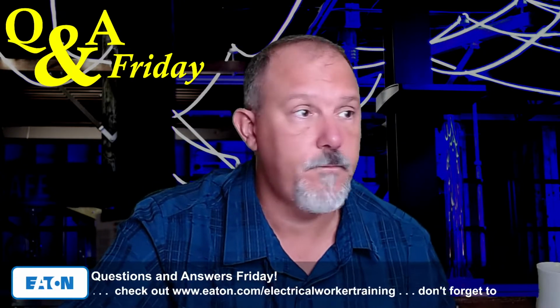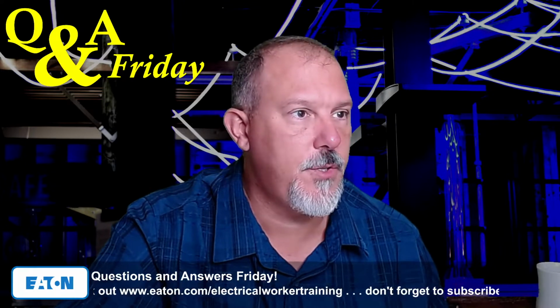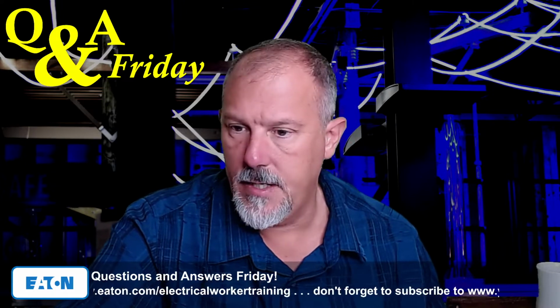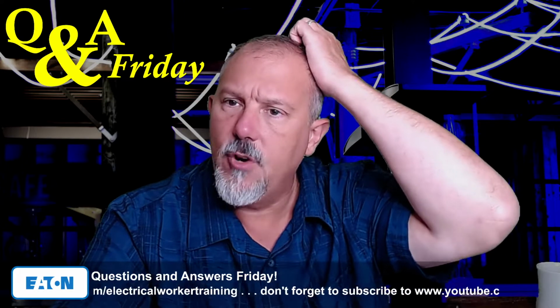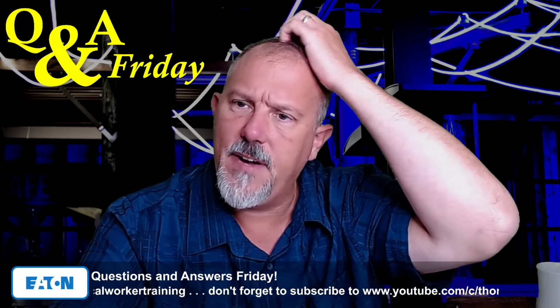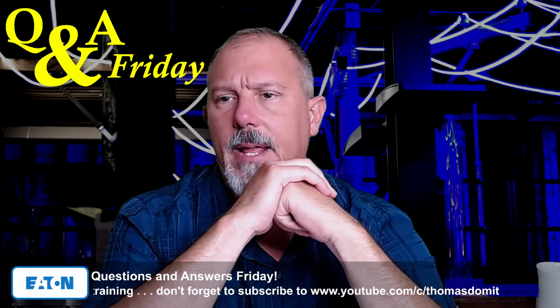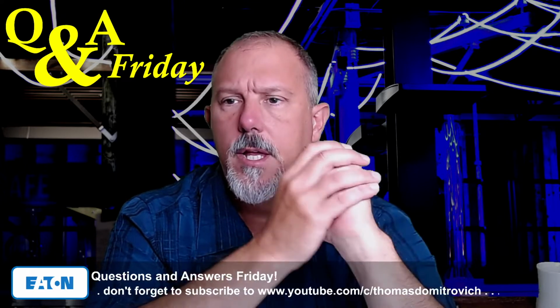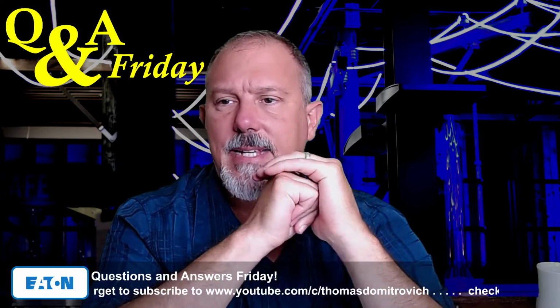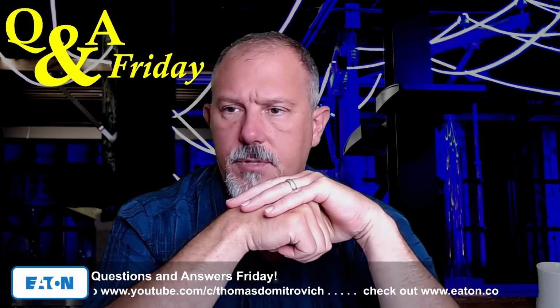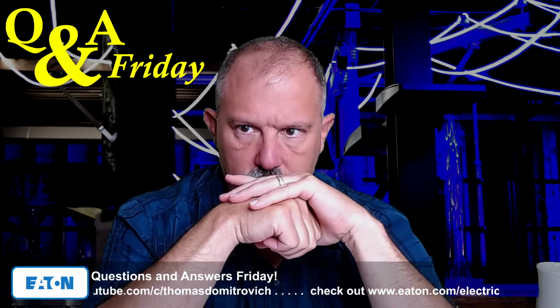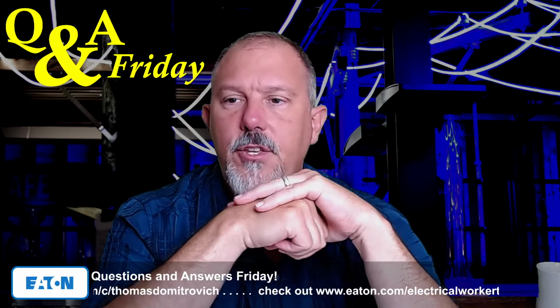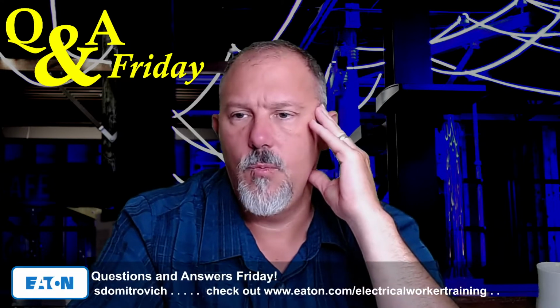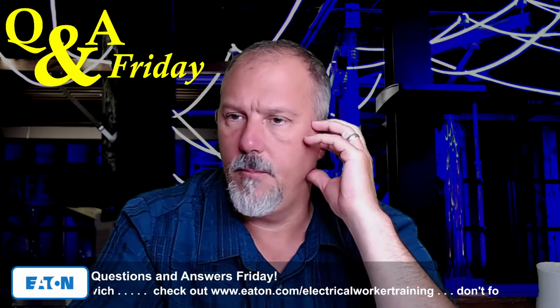Really do. All right, so let's get to, I'm going to close this. Don't save. 1232. I have a question about 100% rated breakers. If I buy a 2000 amp frame 80% breaker and turn long time down to 1600 amps, or even 1600 amps turn down to 1200 amps, could I use this in place of a 100% rated breaker?